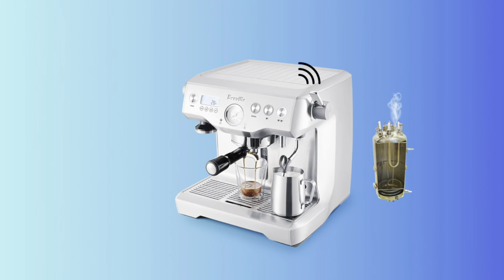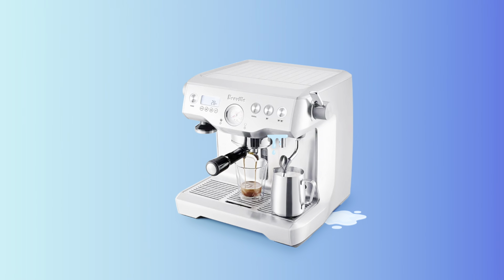Next up are water leaks. Your O-rings might be bad enough that they're letting out water inside the machine. You may see this coming out onto the bench top or around the hot water outlet. If this water gets into areas with high voltage, your mains fuse might be tripping out too.